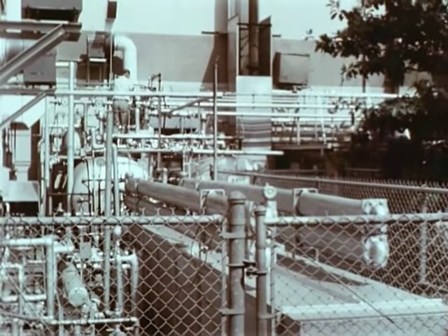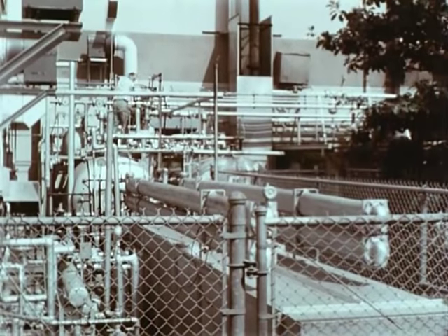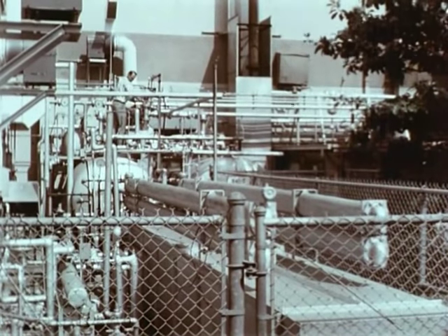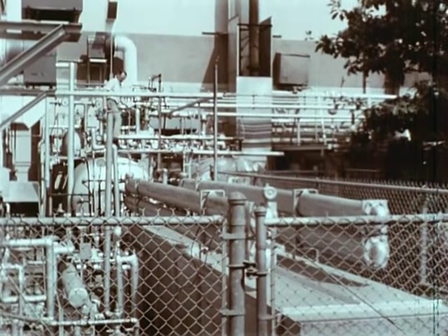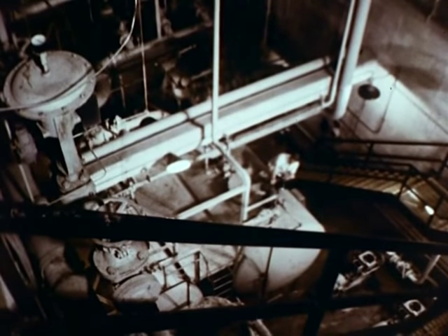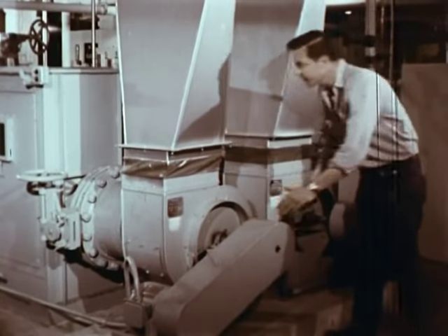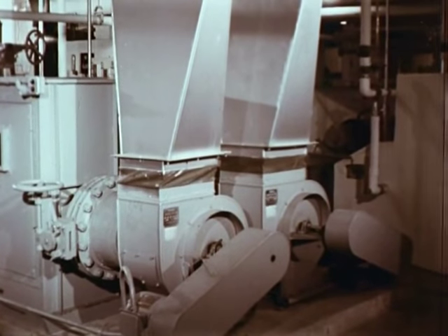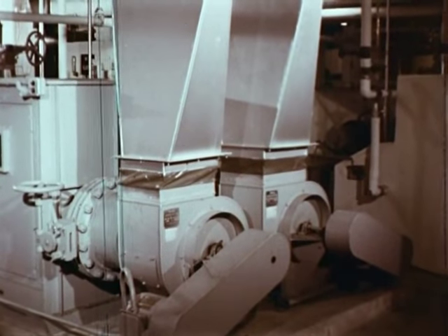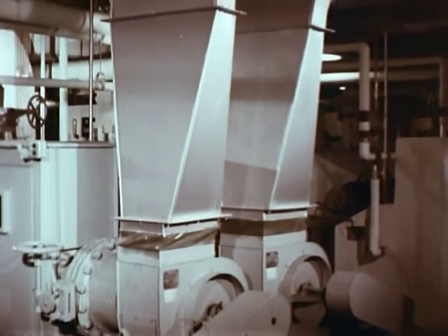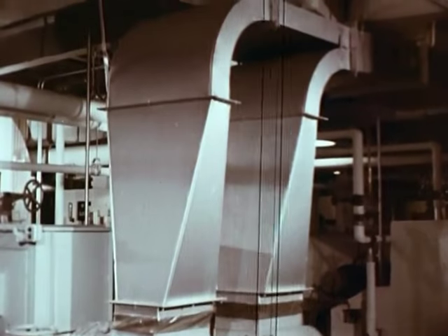As much of the engineering support area as possible should be located outside the contaminated zone, possibly on the grounds adjacent to the building, or in the basement or attic of the facility. Because of the large amount of engineering equipment needed, more than half the total building area is sometimes required. The most important engineering functions are air handling and ventilation, often involving nearly 50% of the cost of the laboratory building.